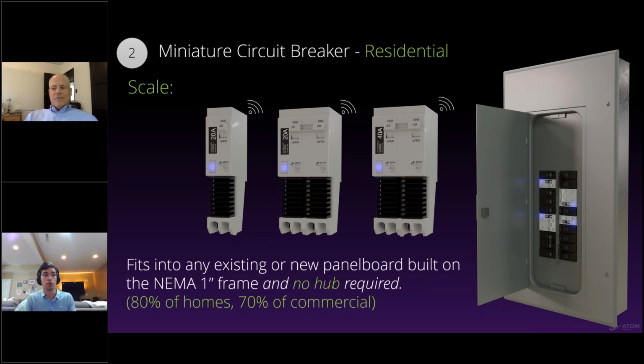Because it operates so quickly, you don't have that high fault current propagating through it, so you don't have those damaging effects. Every time a mechanical circuit breaker sees a fault of 10,000 or 20,000 amps or more flowing through it, that's a lot of magnetic force blowing the circuit breaker apart. We don't see anything like that, so we expect these to last way longer than a typical circuit breaker under any stressful condition.